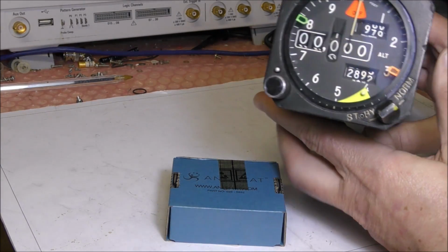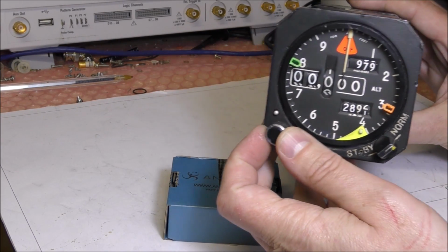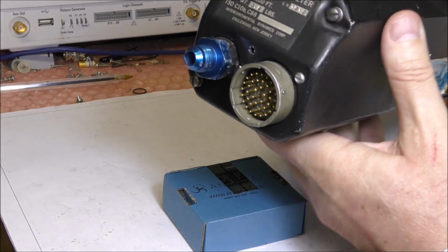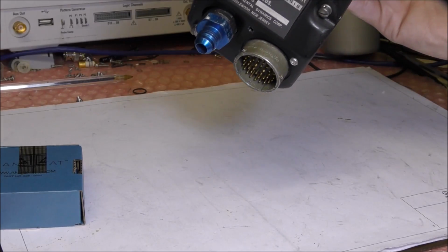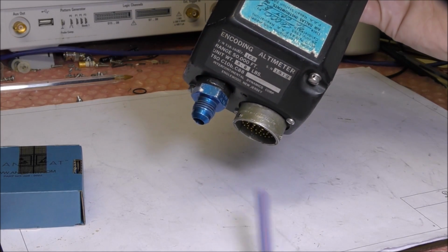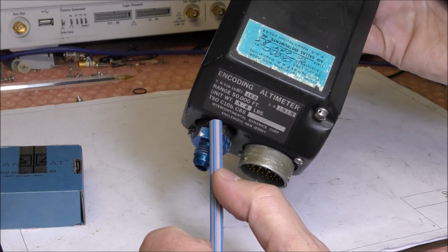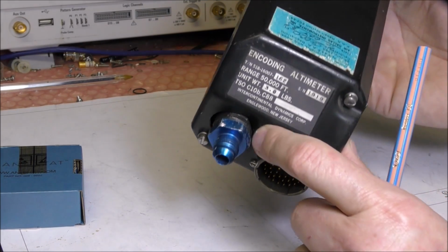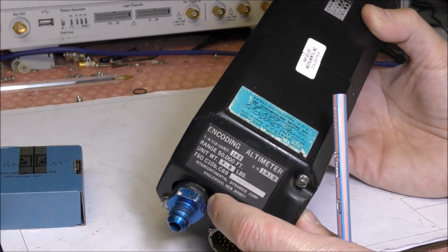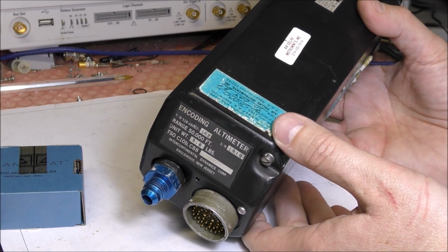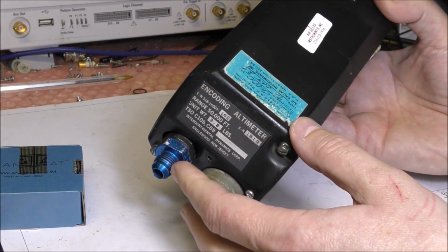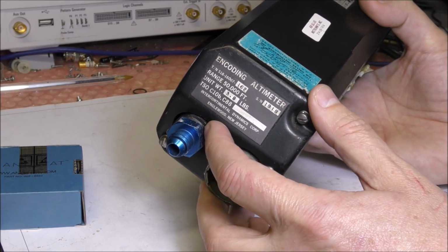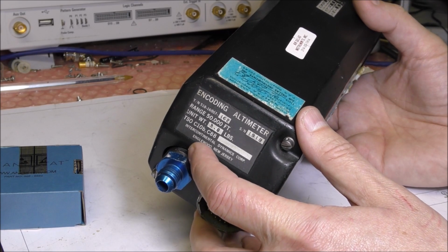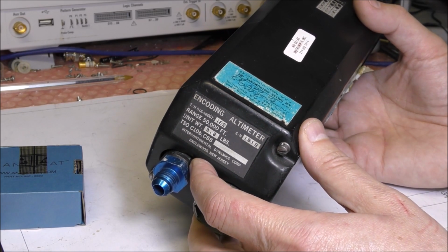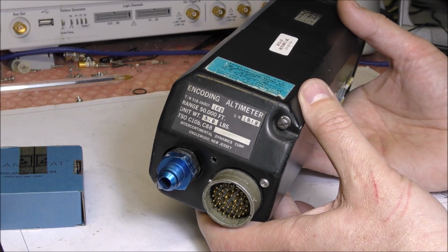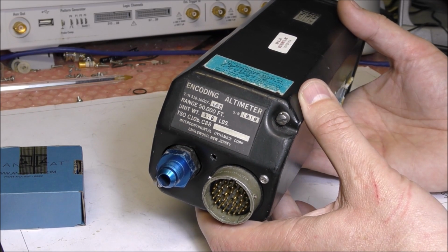So actually, this knob was totally bent, the shaft of this knob. And also, this is more important, when I received this instrument, this pressure inlet was bent like this, approximately. So you can see that there is a deformation of the enclosure here. So I have straightened more or less this pressure inlet. It was very difficult because this is actually the input of the transducer. So this is a very sensitive part. So I hope that there is no major damage on the mechanical stuff.